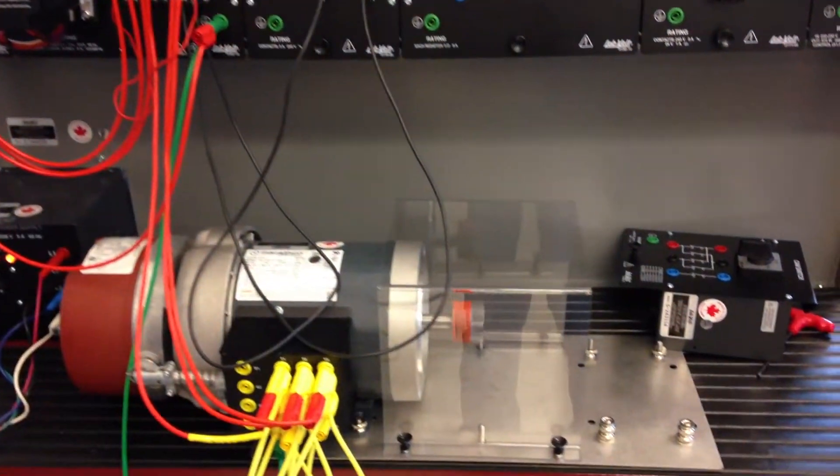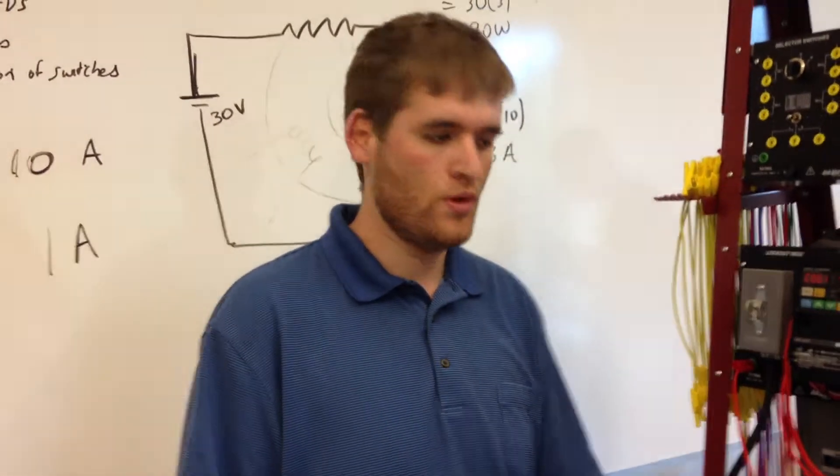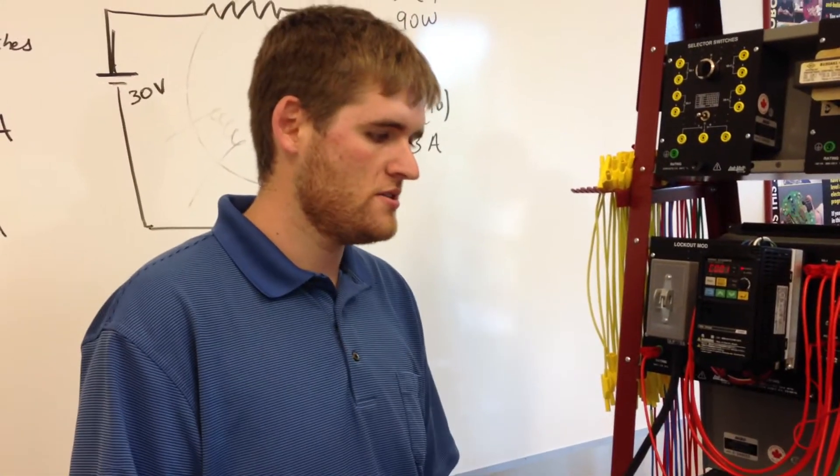And the motor is slowing down quicker than it would if it were coasting, but not as quick as it would with the friction brake engaged. So that is DC Braking using an Omron SysDrive VFD.